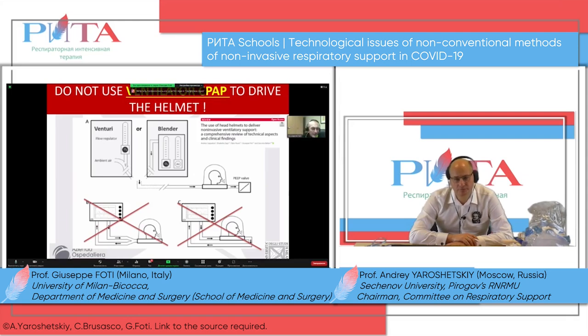Yeah, okay, they have it here, right? At this point. Yes. So during expiration, flow goes through this limb here or through the whisper flow, and CO2 accumulates inside the helmet. The only way to avoid accumulation of CO2 inside the helmet is pushing air inside the helmet through a PEEP valve, finish. If you put the expiratory limb going inside the helmet, it can be dangerous.